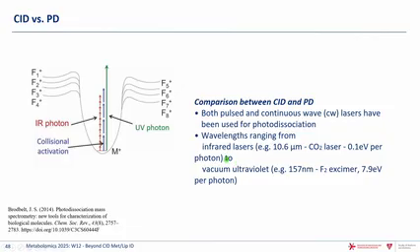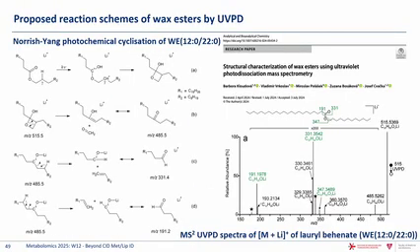So 50 years ago, they were using this CO2 laser, which is just 0.1 electron volts per photon. But now they moved to ultraviolet lasers. If you think about, let's say, 157 nanometers, it's getting 7.9 electron volts. I think in the commercial instruments they're using 213, if I'm correct, which is overlapping with the double bond of CC and CN.